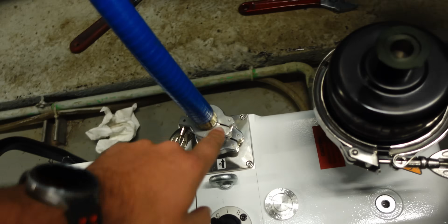Pressure test finally went good. We had a handful of small leaks we didn't anticipate, not stuff we were working on directly, but small things that came up because we were moving stuff around. For example, I should have thought about it, but didn't: the terminals for the oil pump motor ended up leaking, which makes sense once I thought about it, because that flange is usually hot, 120 to 140 degrees, but it's been cooled down for 2 weeks now, probably only about 70 in this room. That's a big change in temperature, which changes the metal quite a bit, so it's not surprising some of those leaks formed in a part of the system that's usually warm.